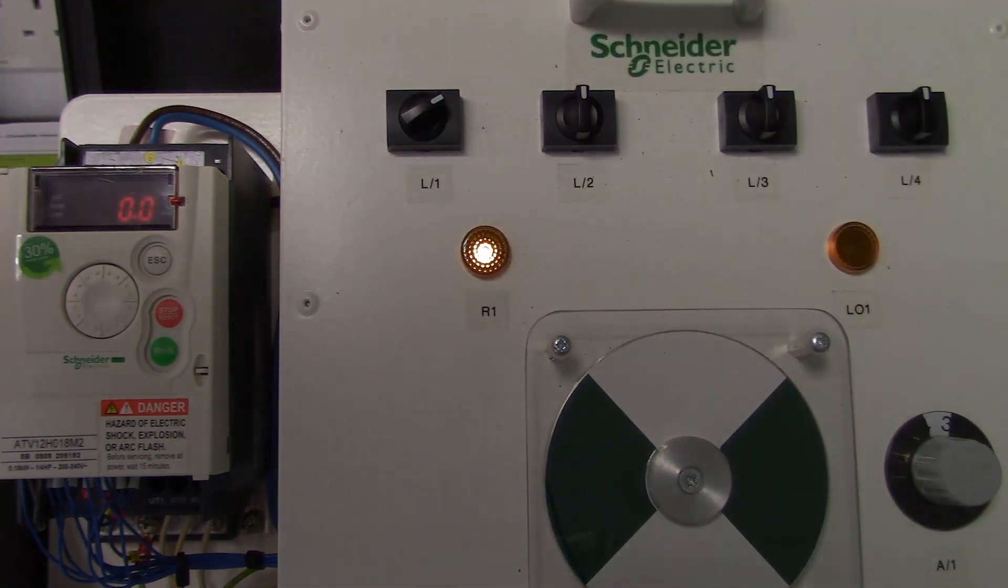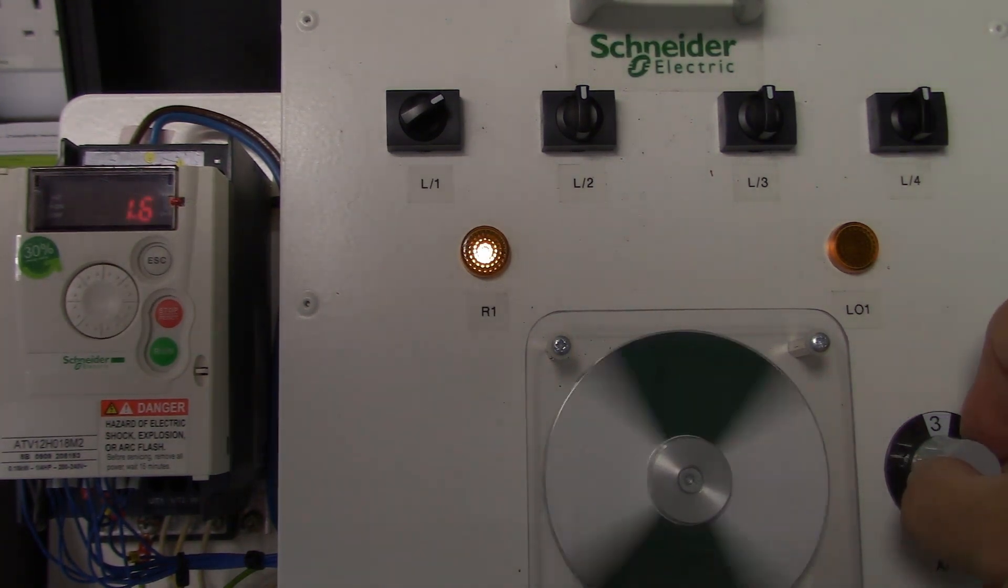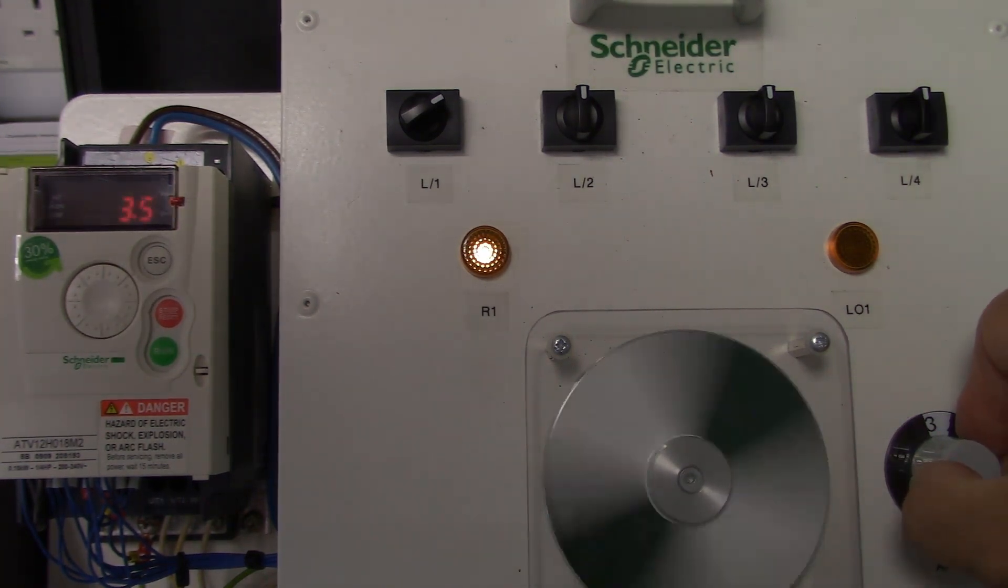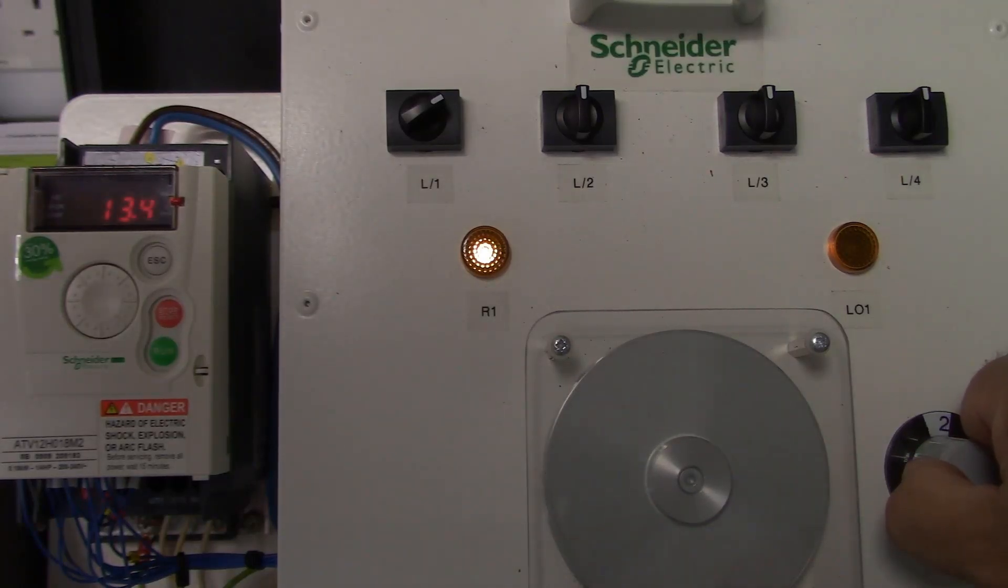We can now start the drive using logic input 1. We now go to a running state. By reducing the feedback the drive will speed up. And if we raise the feedback the drive will now slow down.